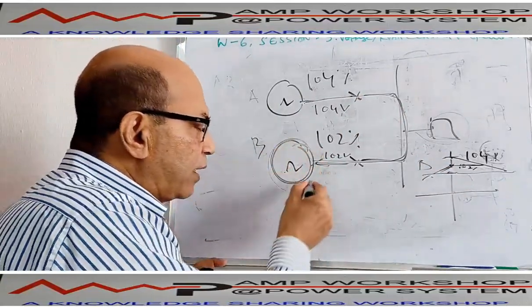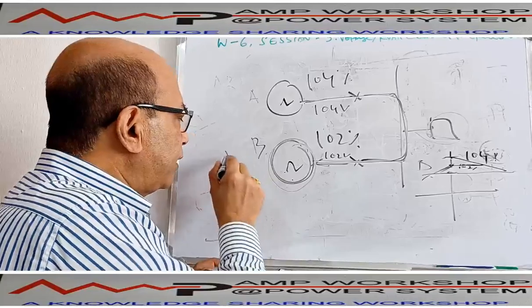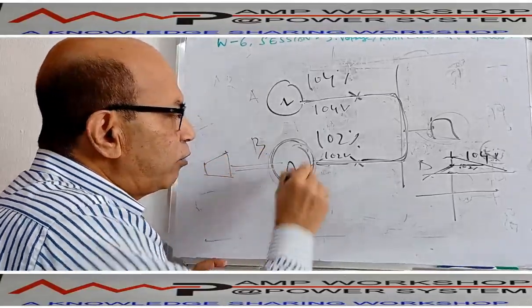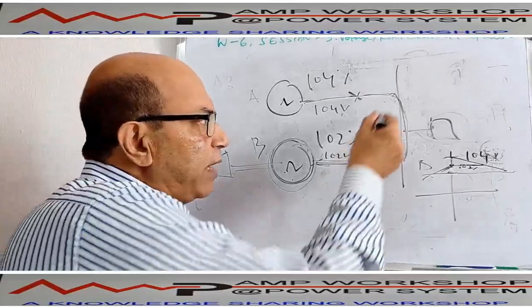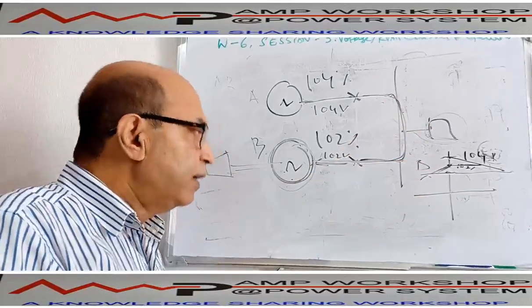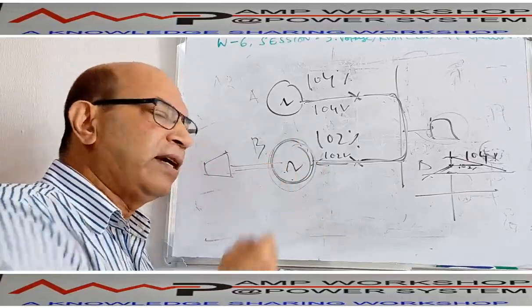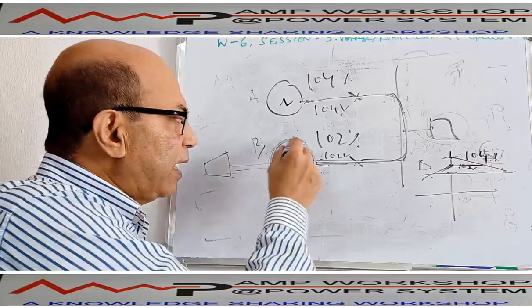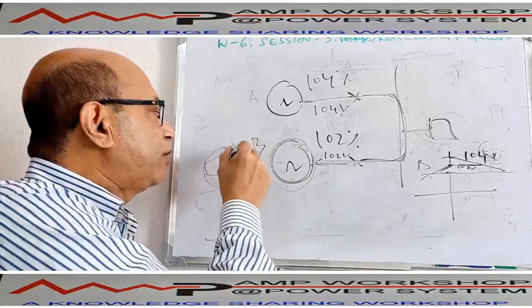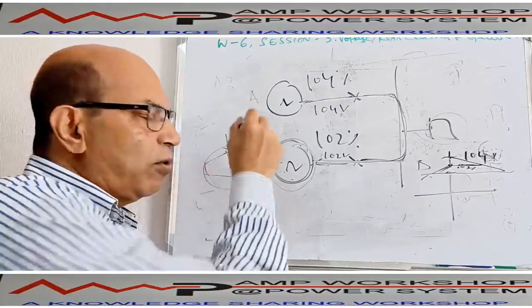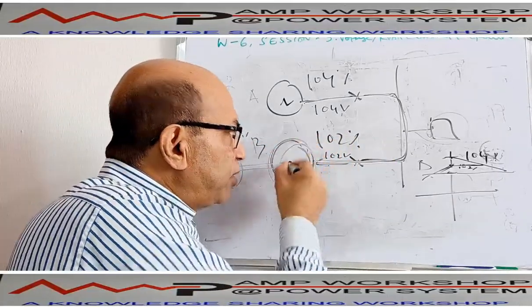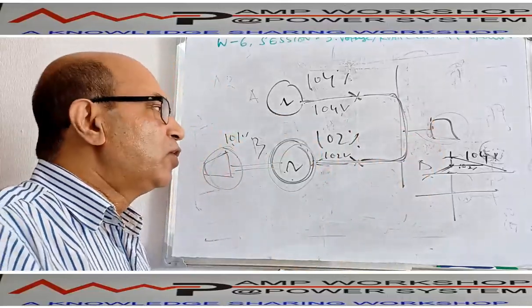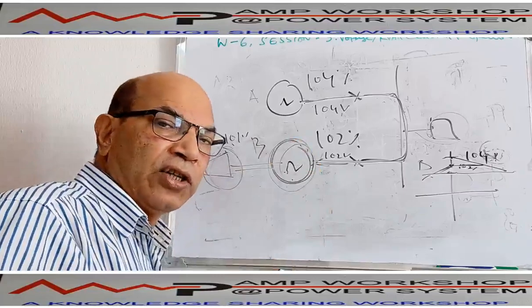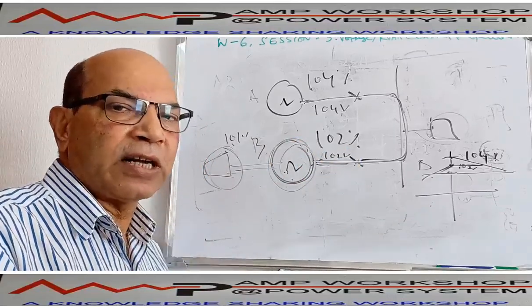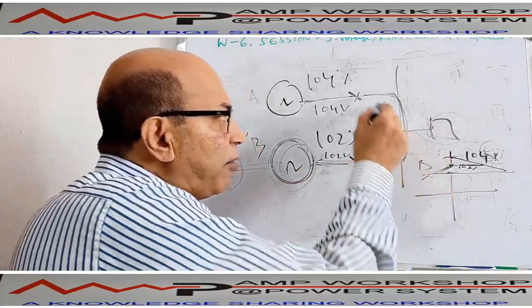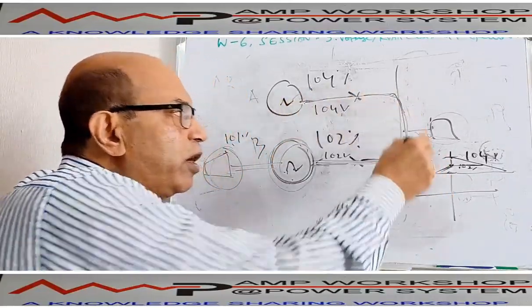And you know, a generator is rotated by a turbine. It is coupled with a turbine and rotating at a certain speed. At the same time, it is taking reactive power from the system. Then this generator will not act as a synchronous generator. It will act as an induction generator, because maybe this machine is running at a higher speed, with the droop mode maybe 101% droop, so it is running over the synchronous speed. At that time, the machine is taking reactive power from the system, so the machine will act as an induction generator. That is very dangerous for us. Instead of giving reactive power, it will draw reactive power from the system, and the system voltage will also get dropped.